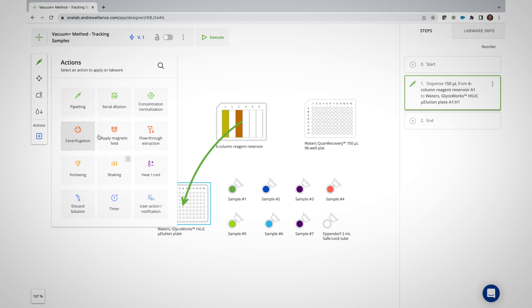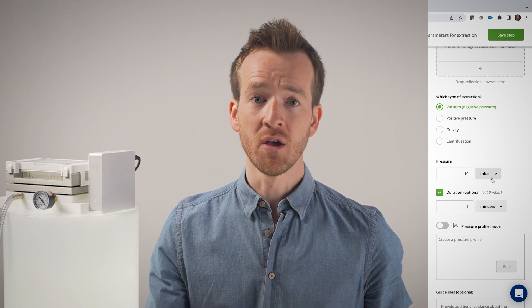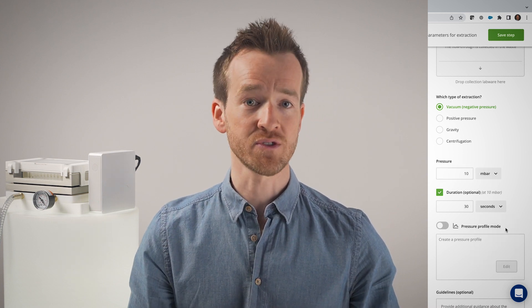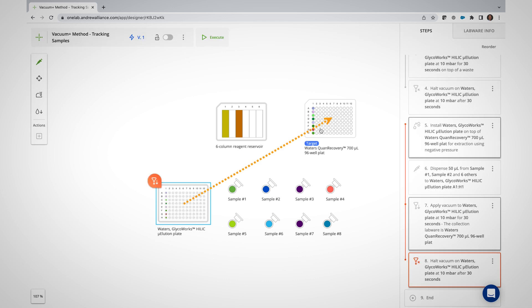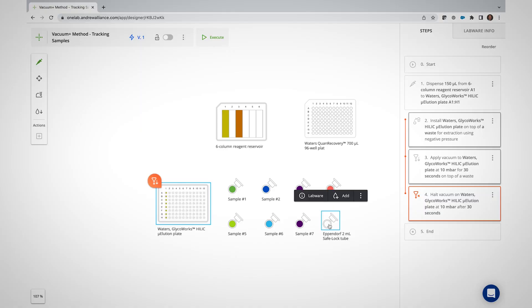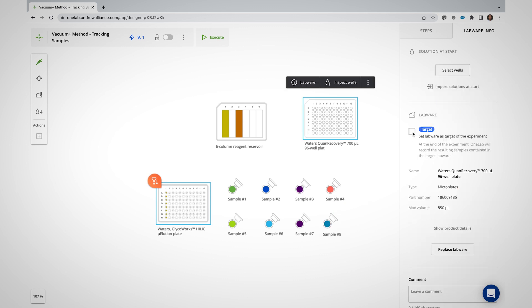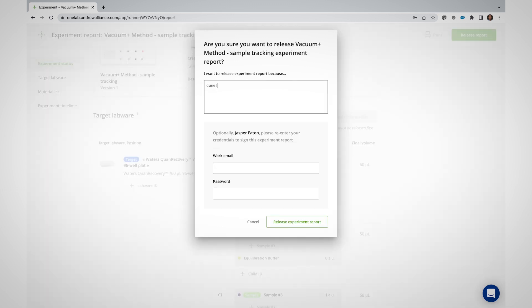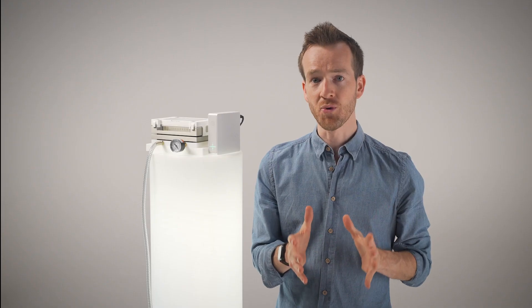Next, click on the Actions button on the left panel. Select Flow Through Extraction from the list, and drag and drop the consumable you want to apply the action to. The Vacuum Extraction setting is selected by default, so you can directly scroll down to specify the desired pressure setting and duration. When also selecting a collection labware in this window, OneLab will automatically understand that you're looking to transfer the solutions and samples that pass through the elution plate into the collection plate for any subsequent steps, or for sample tracking purposes. If sample tracking is important to you, when designing a method, make sure to tag your samples accordingly and designate a target labware, like the collection plate we've just selected. This will ensure that you can electronically extract sample information like final position, concentration, and composition at the end of your experiment.